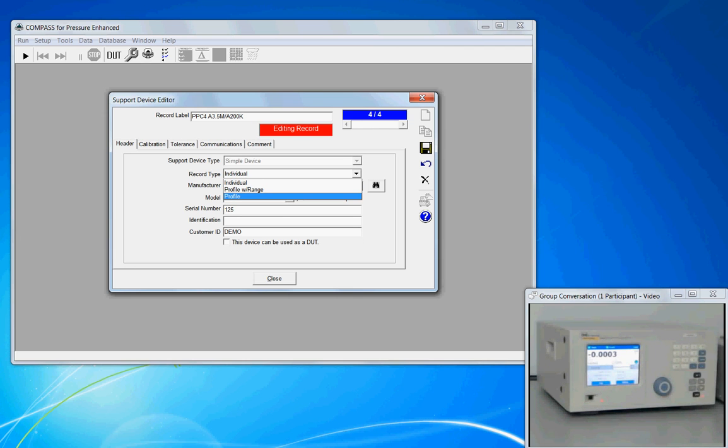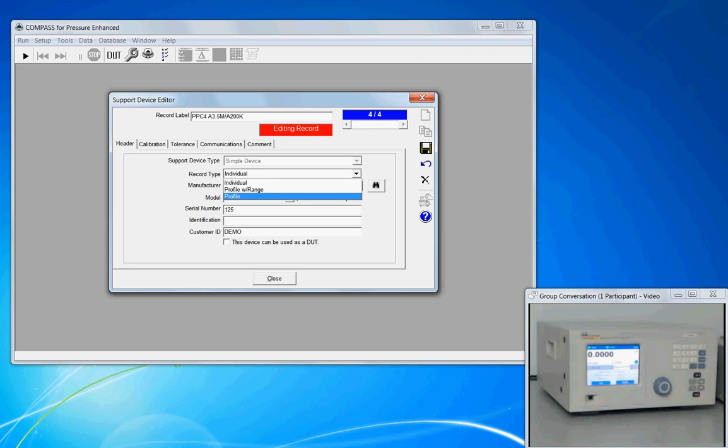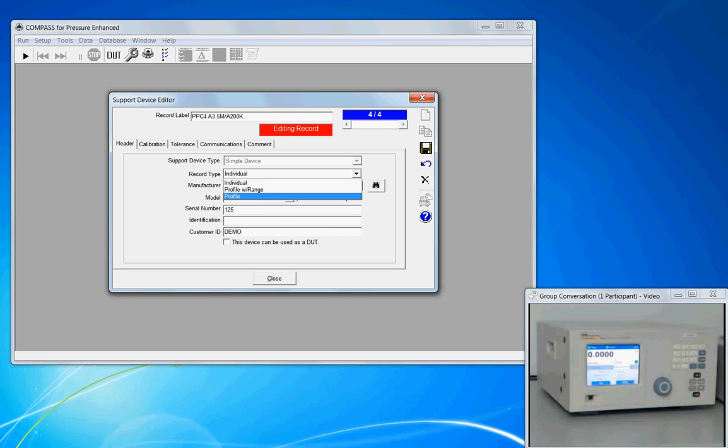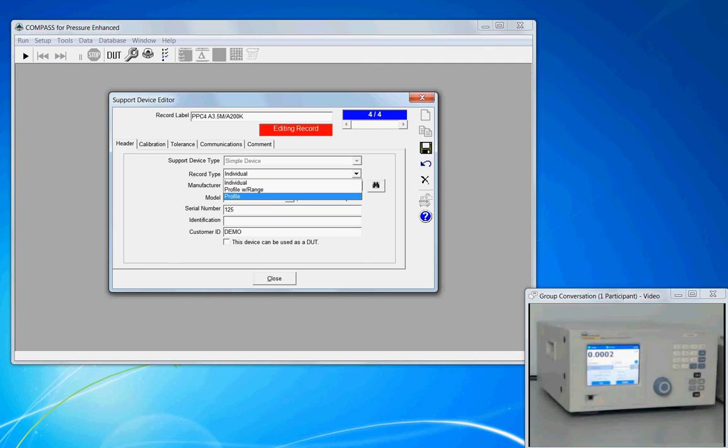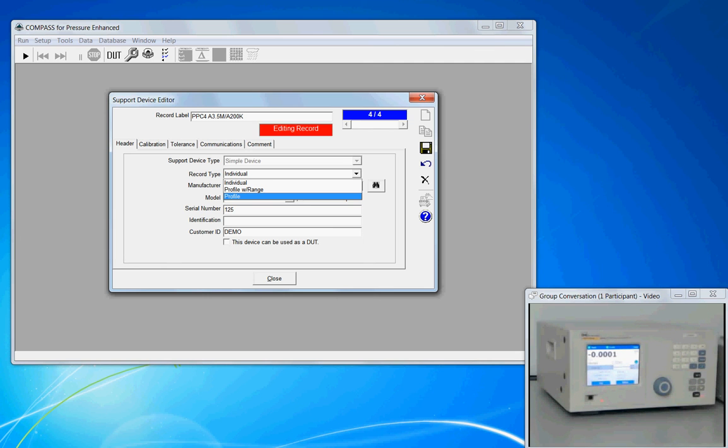It just creates less entries into the database, and so if I have four PPC-4s, I could use a profile, make a generic, and have one record for all four devices. The unique identifying information, such as serial number and asset number, would be prompted at the time that the device was used for a calibration.